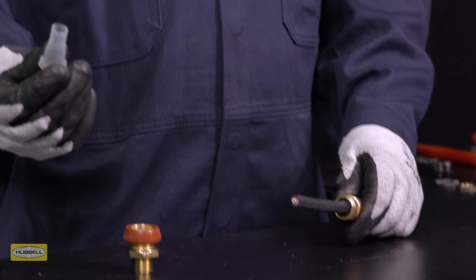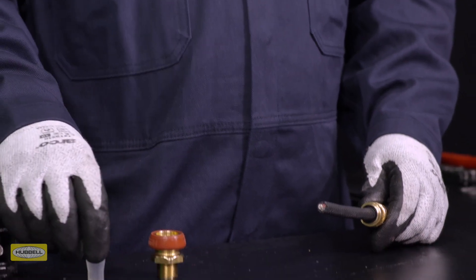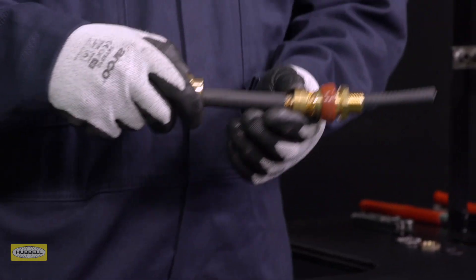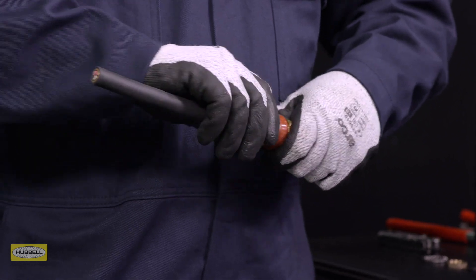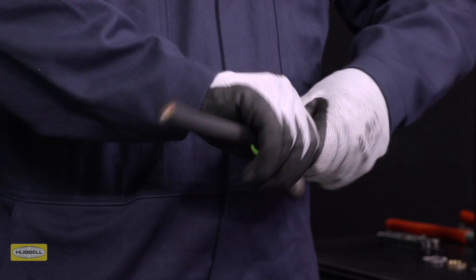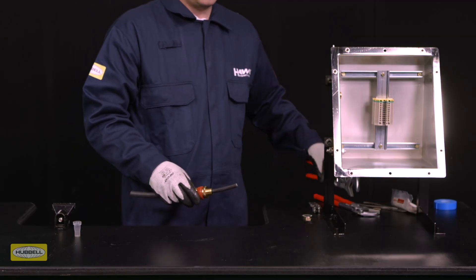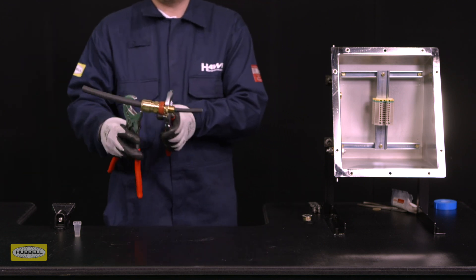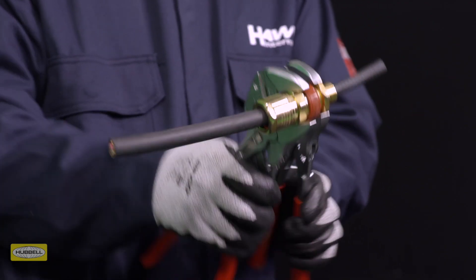Ensure the compound pot is removed from the assembly. Slide the entry over the cable. Slide the middle nut up to the entry and hand tighten. Support the cable to prevent it twisting. Grip the entry with a spanner or wrench. Use a second spanner or wrench to tighten half to three-quarters of a turn.